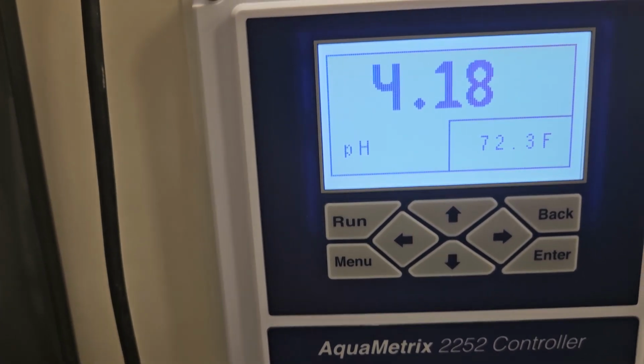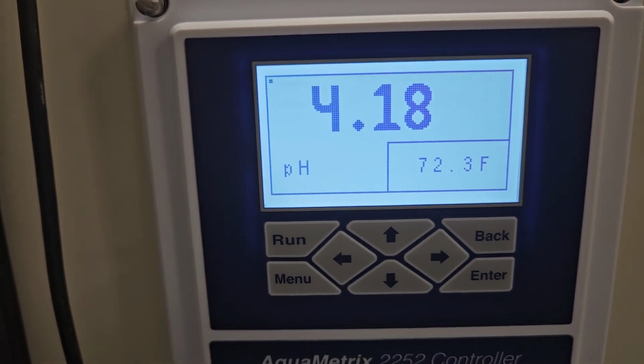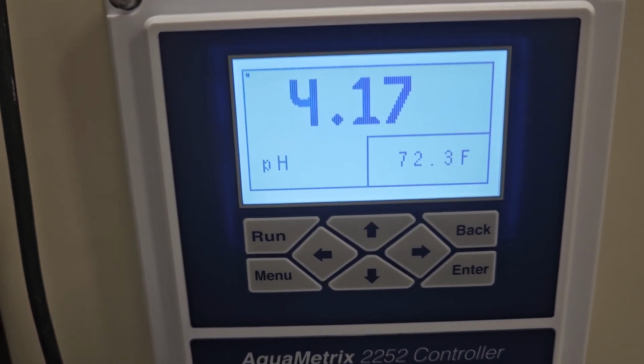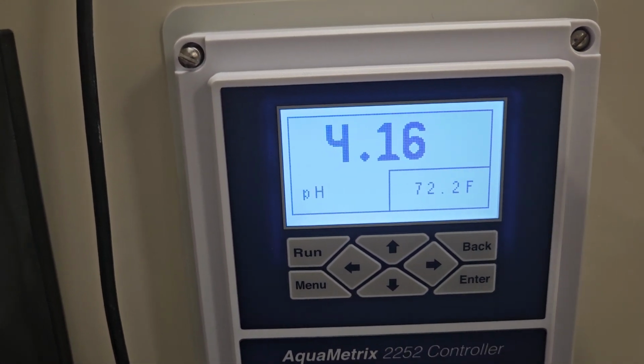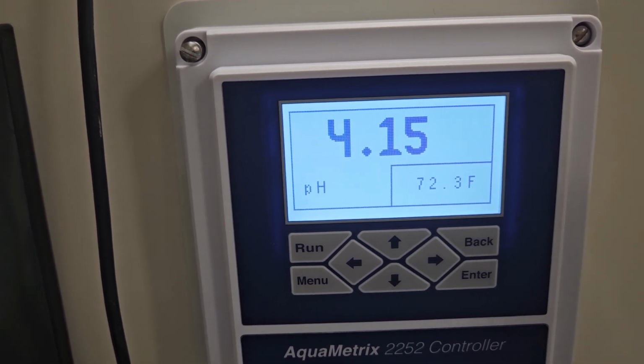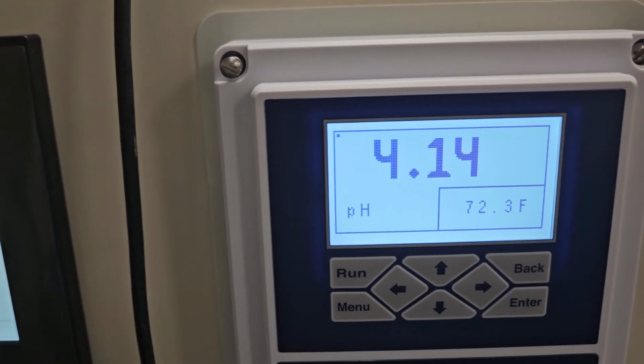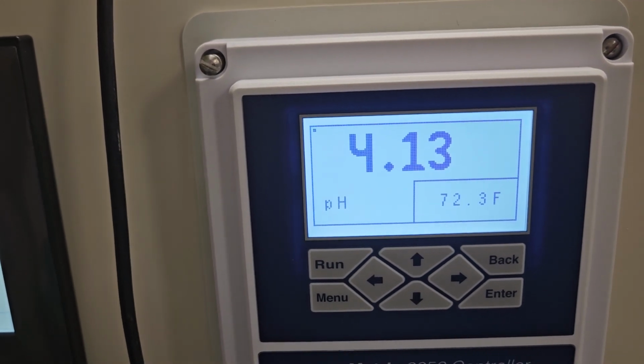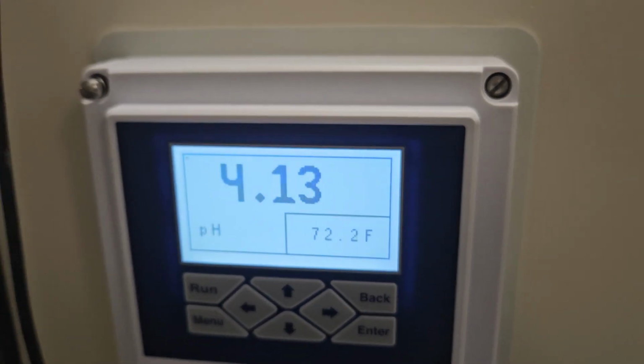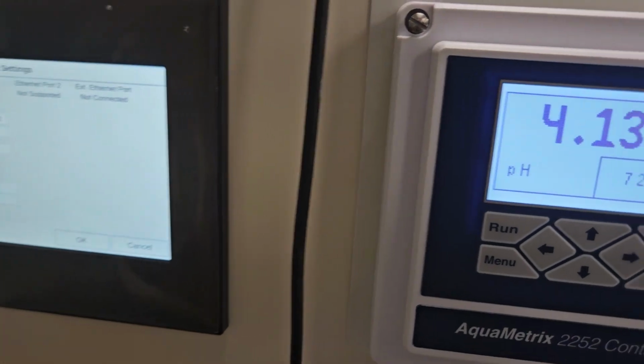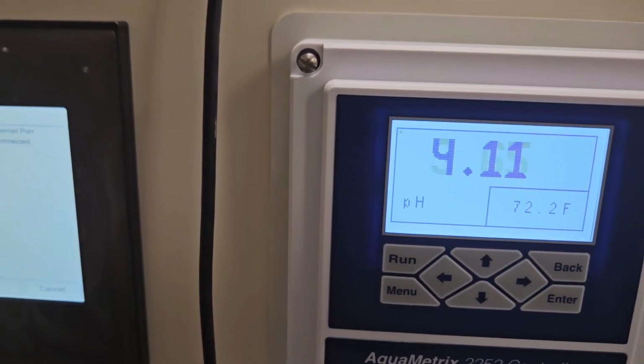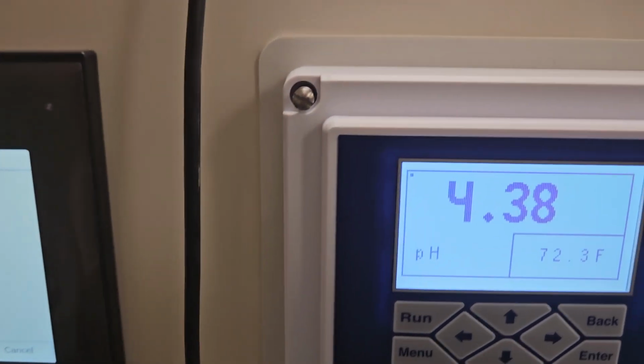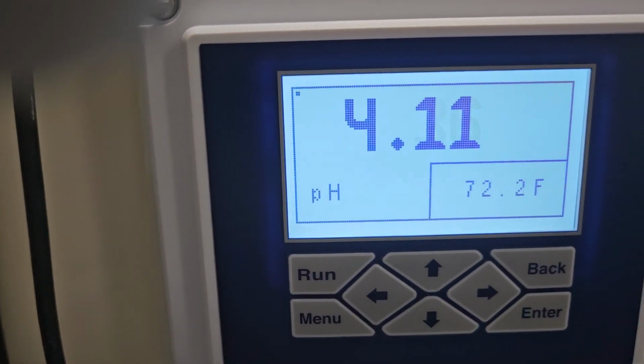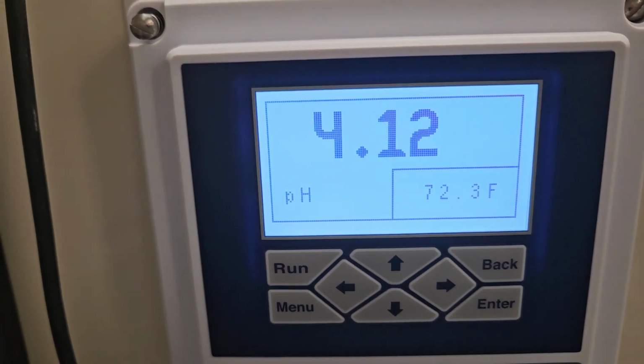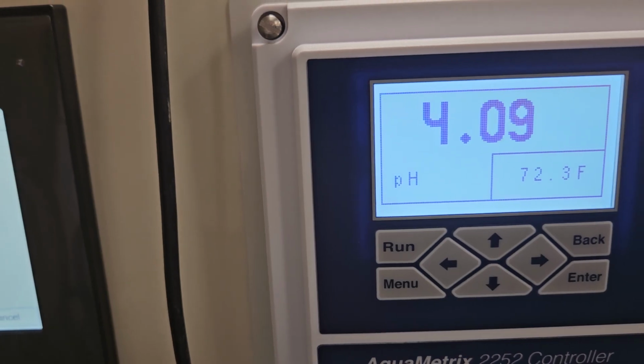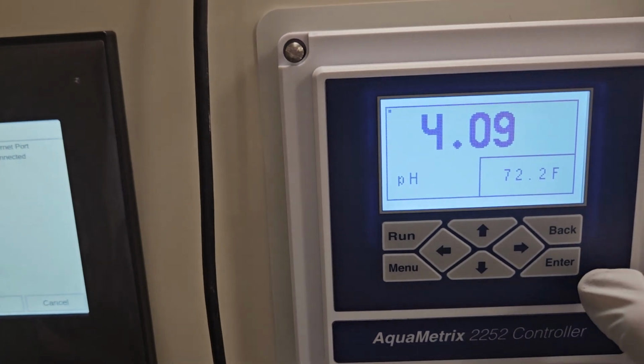I'm supposed to wait again at least another minute so that the number stops moving around so much. If it fluctuates between two of the same numbers, like 16, 17, 16, 17, you can pretty much say it's there. But if it's actually drifting, you want to let it sit and attain a constant reading. You can move the probe around a little in the cup to get a good mix and a good reading. I'll pause the video to let it achieve a stable reading. Okay, it's pretty much stabilized right around 4.10.